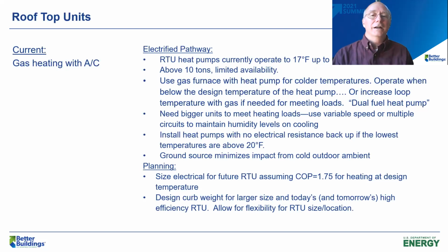Some of them are called dual fuel, where they have a gas furnace that's built into them, which may operate when the design temperature is below what the heat pump can handle. There are other strategies too: if you do need gas, you increase loop temperatures when you do it, right? And again, these are a kind of dual fuel heat pump. You may need bigger units to meet the heating loads. We're accustomed to a cooling load, and especially as you move further north, you say, well, what is the delta T between inside and outside? It might be 25, 30 degrees, even on the hottest day, and you could add another 30% to that to deal with humidity loads.